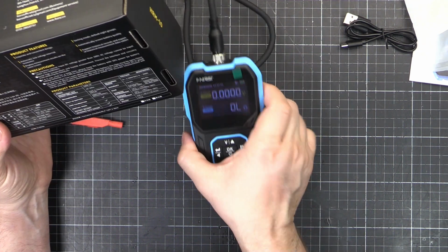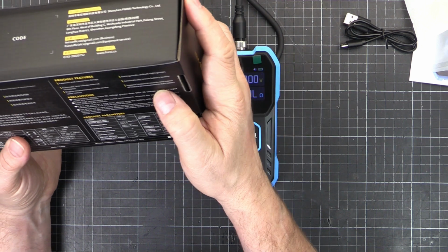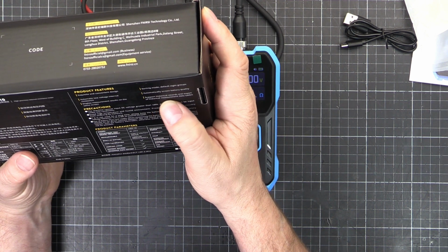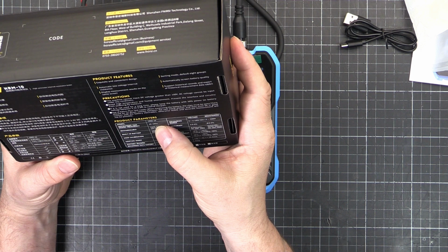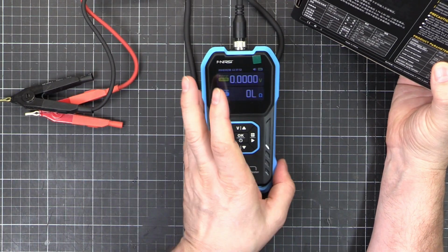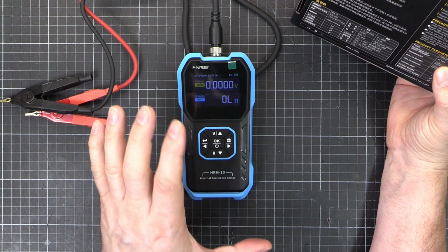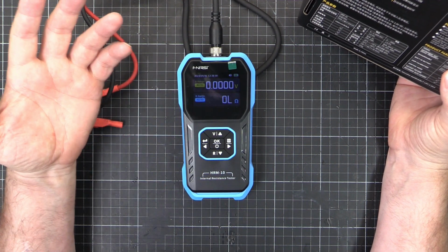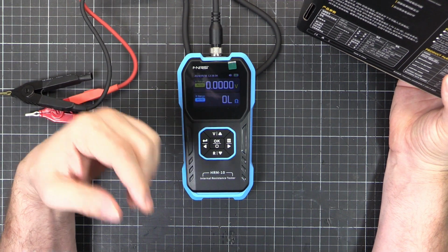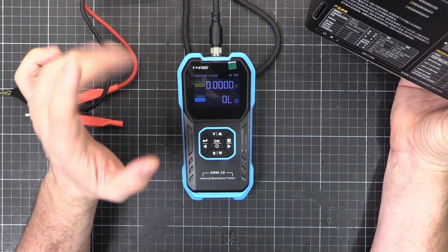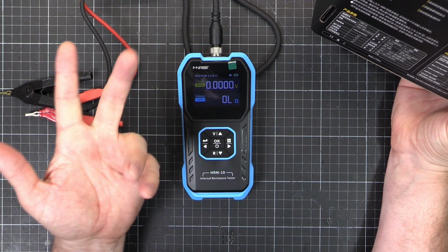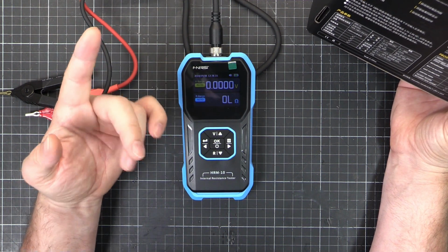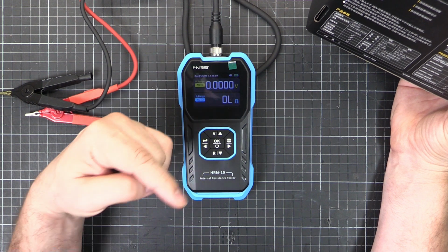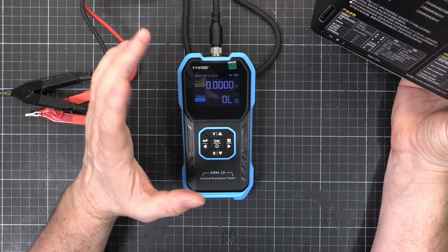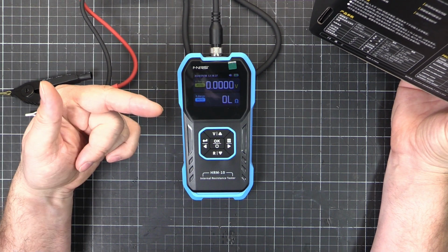Automatically screen battery quality. So I guess that'll tell you if the battery is good or not. Or the battery cell. Support historical records and export of historical measurement data tables. Yes, that's the CSV export. It is instrument test signal frequency. Okay, so this tests with an AC signal, 1 kHz AC signal. This is the industry standard of testing batteries more accurately than with DC. Some cheap testers will do a DC resistance test. That's not so accurate, because you end up charging and discharging the battery depending on which way you're testing and all that sort of stuff. You get the chemical effects in the battery. But with an AC signal, 1 kHz, it's going back and forth, so it negates any of that charge discharge sort of effects of the battery, and you get much more accurate internal resistance result.